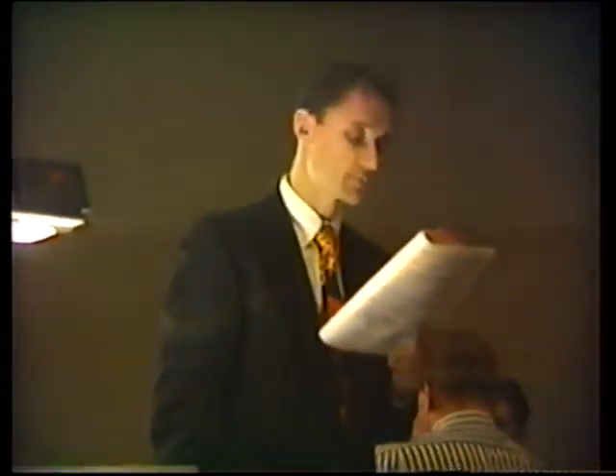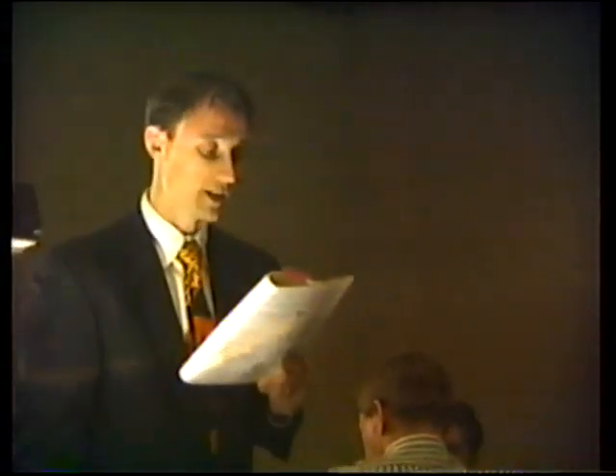Now here's where it gets interesting. Performance criteria, survivability. This is what the sprinkler system must be designed to. The following conditions shall be attained at a distance of 5 feet above the floor level in areas where sprinklers are required. A, the temperatures do not exceed 150 degrees Fahrenheit. B, instantaneous carbon monoxide concentrations do not exceed 10,000 parts per million. C, cumulative carbon monoxide concentrations do not exceed 25% the carbon monoxide hemoglobin level. And D, the oxygen concentration is maintained at 14% or greater. Little difference than just saying, hey, I got a light hazard or something that's designed for 0.1 over 1,500 square feet or something. Okay? Those are performance objectives.